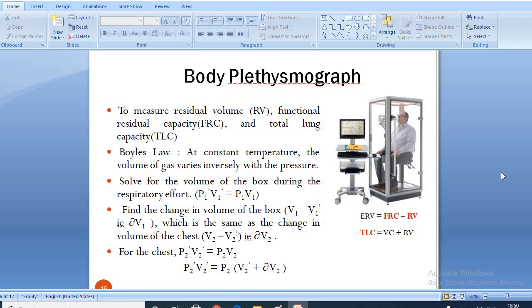In a traditional plethysmograph, the test subject or patient is placed inside a sealed chamber, which is an airtight box with a single mouthpiece. Utilizing Boyle's law that is at constant temperature, the volume of gas varies inversely with the pressure. The ratio of the change in lung volume to change in mouth pressure is used to determine the thoracic gas volume.